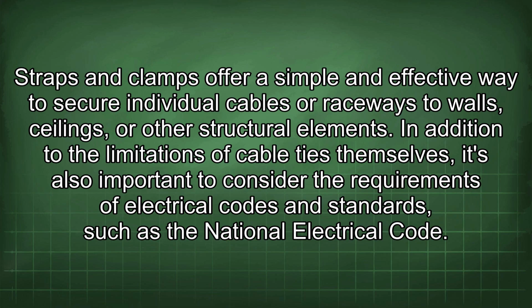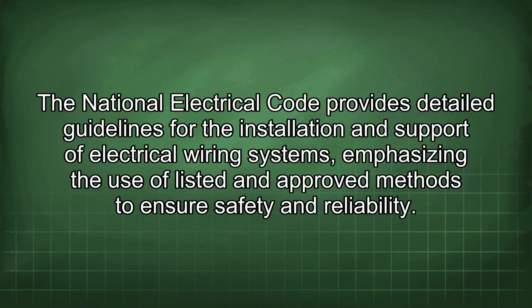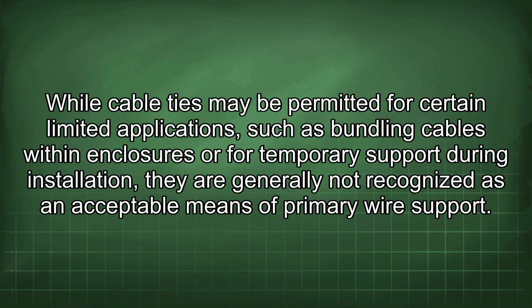In addition to the limitations of cable ties themselves, it's also important to consider the requirements of electrical codes and standards such as the National Electrical Code. The National Electrical Code provides detailed guidelines for the installation and support of electrical wiring systems, emphasizing the use of listed and approved methods to ensure safety and reliability. While cable ties may be permitted for certain limited applications, such as bundling cables within enclosures or for temporary support during installation, they are generally not recognized as an acceptable means of primary wire support.